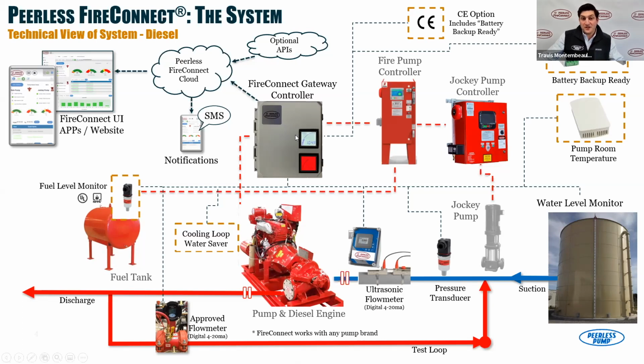What FireConnect is and what it does, it is the IoT output effectively for all of this information. So all of these components are basically data outputs. There's data coming out of the controllers. There's data you can gather from the pump, from the water storage tank, from the fuel level, for example, pump room temperature over here on the right. There's so much data there, and that all flows through FireConnect. So we've got this hardware piece, this FireConnect gateway controller that's in the middle. It's connecting to these controllers here via a Modbus connection. It's connecting to digital and analog inputs for other accessories here. And it's taking all of that data into this gateway controller. And we've got an IoT board within it.